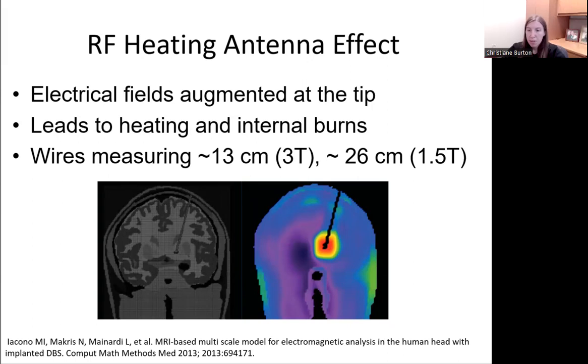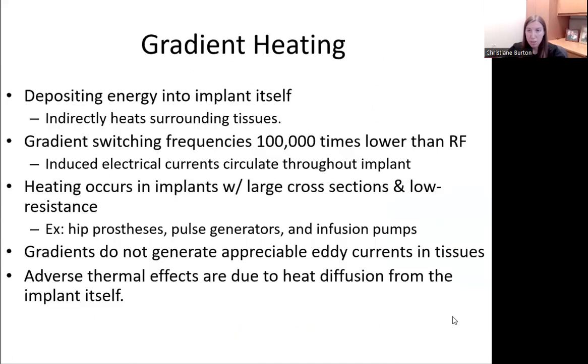One special example of localized RF heating around an implant is known as the antenna effect, seen in elongated implants like wires or electrode leads whose lengths are between 1/4 or 1/2 the RF wavelength. For MRI, wires measuring about 26 centimeters at 1.5 T or 13 centimeters at 3 T are the most likely to create heating problems. In this scenario, electric fields can become augmented at the tip of the device, leading to heating and the possibility of internal burns.